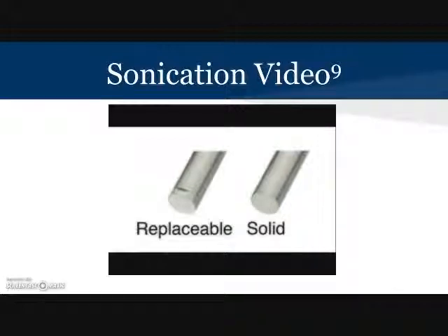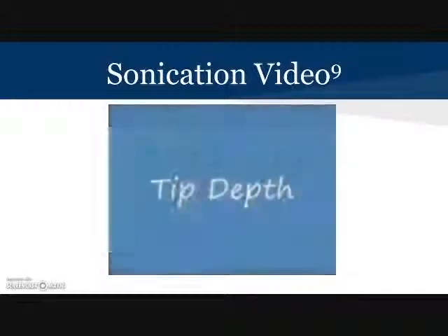So when should you not use a replaceable tip then? The answer is whenever you are sonicating a solution that contains organic solvents, alcohols, or any low surface tension liquid. The liquid will seep into the threaded tip and loosen it, causing the sonicator to overload. Solid tip probes can typically be used for any type of sample.